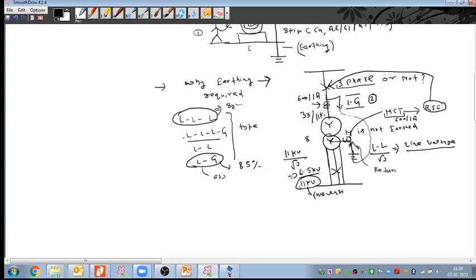Yes, this is the convention. But when you go to the calculations, you should know the fault current that is coming. So I can put the NCT the same as the phase CT, because if I go to the REF, we do the matching of the phase CT and the NCT, and we do the current subtraction here, and then we give this output current to the REF, which we'll cover in the protection part. So we also take this NCT similar to the REF phase CT if we are doing high impedance type protection. And this is the convention that we take the NCT as the phase CT.